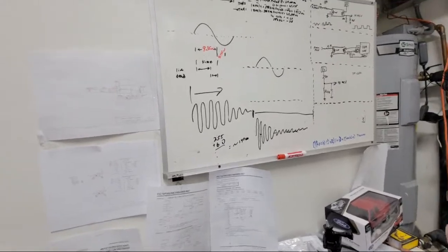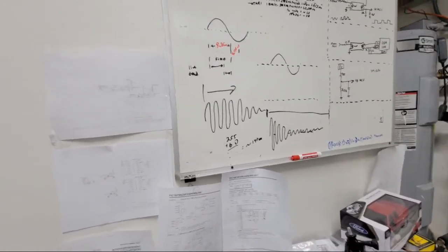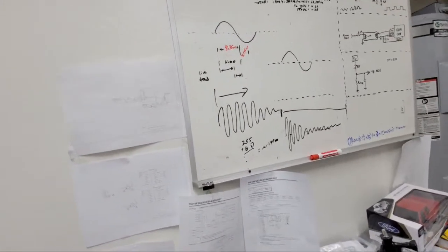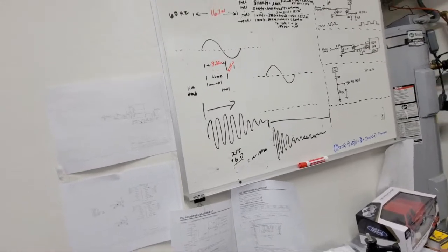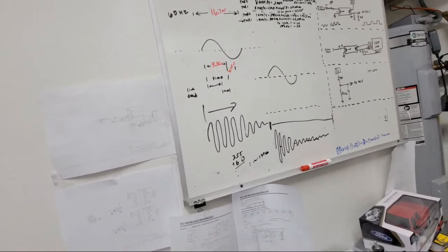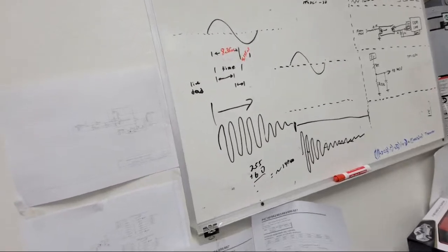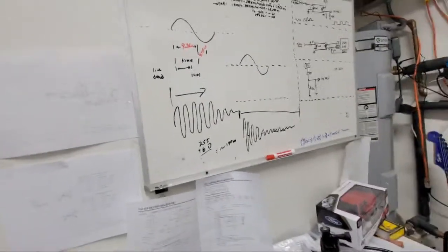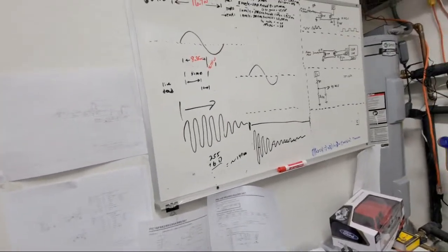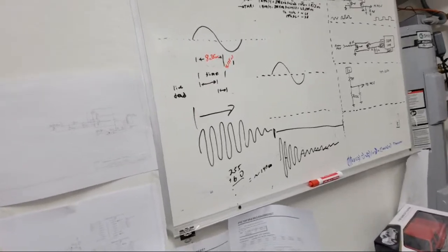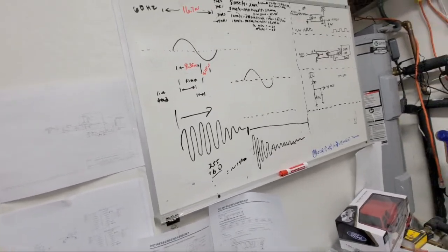They either put a PTC in series with the start capacitor, which is worthless on a restart because it totally has to cool off to work again, or they were using a circuit board that was a fixed 1 second on no matter what. If you have that extra torque, that could be like 5 times too long to be holding it on, and that's bad for the start windings.